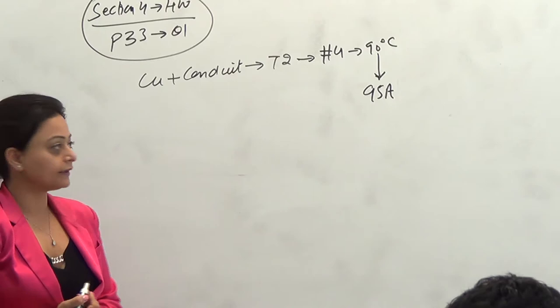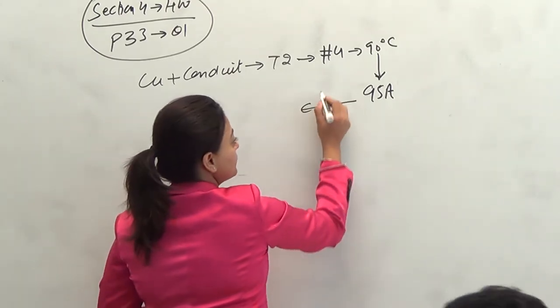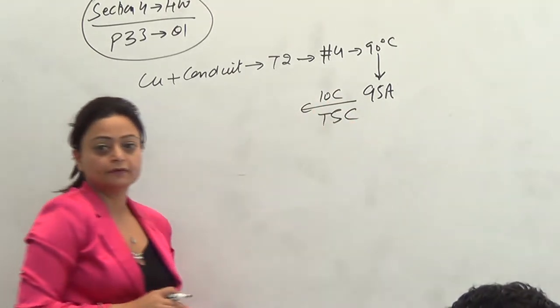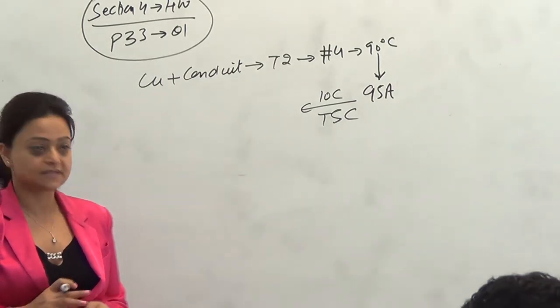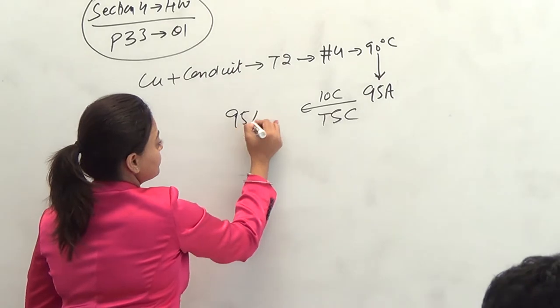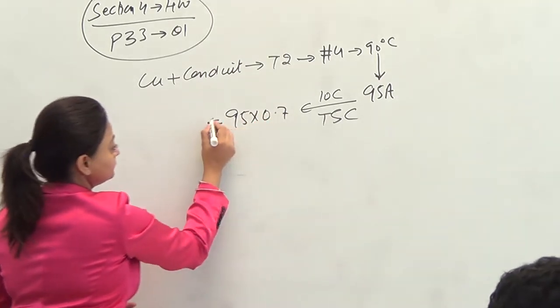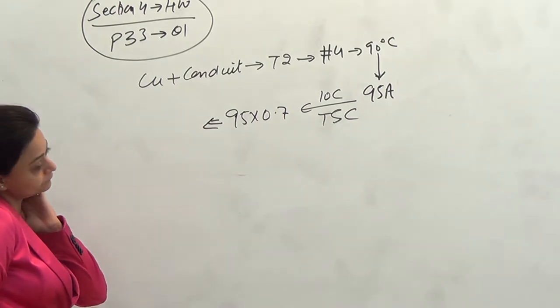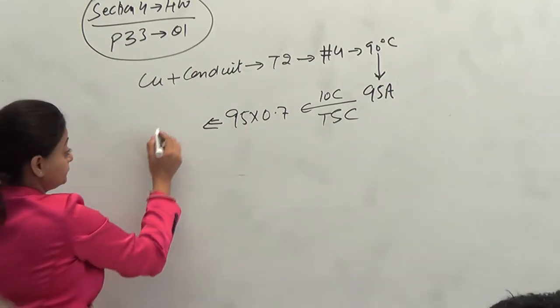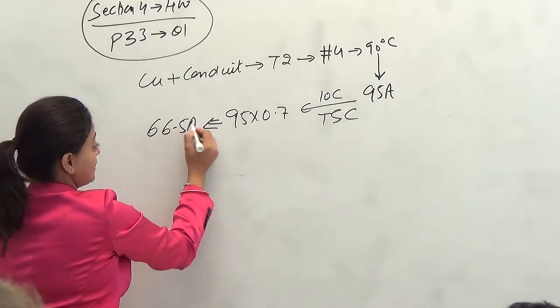How many wires are there? 10 wires. So, I will need it using Table 5C. What is the derating factor? 70%. So, 95 times 0.7 leads to? 66.5 amps.